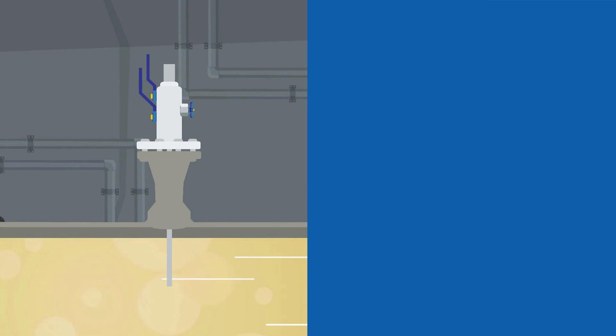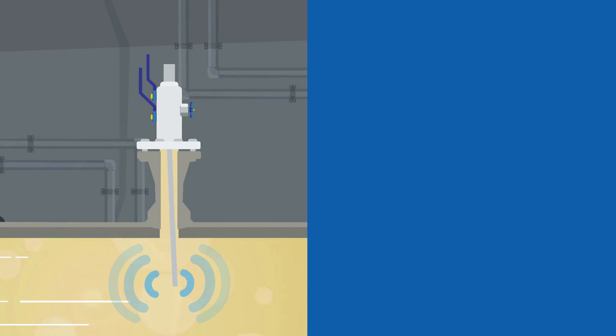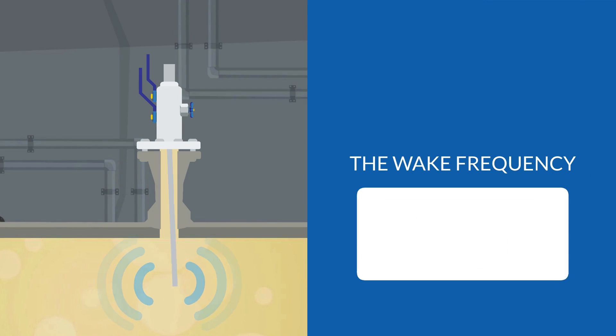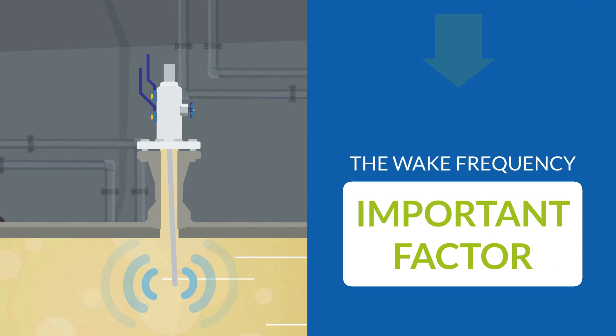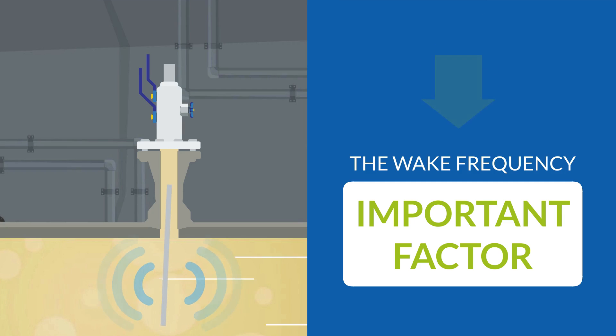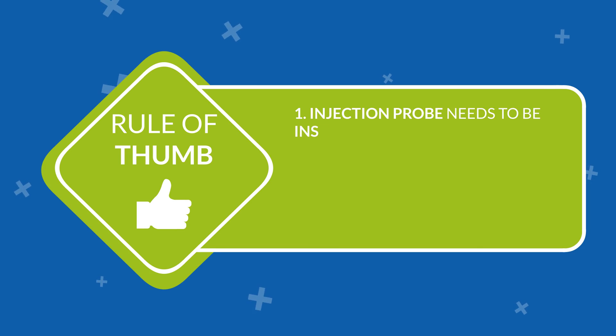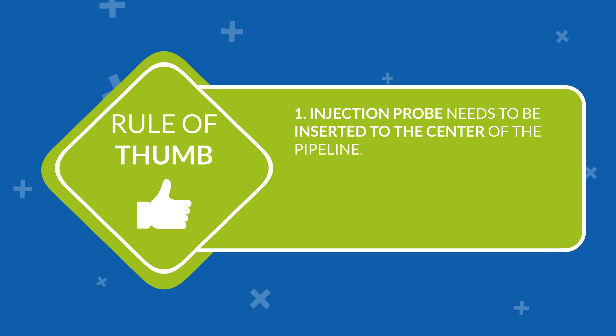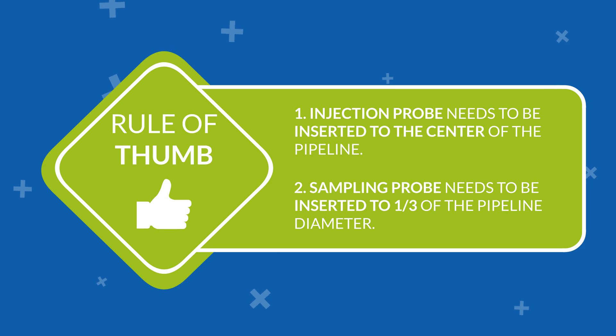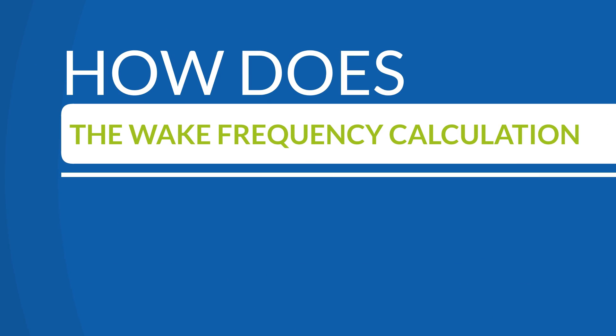Considering that an object inserted into the pipeline can prove disastrous if not properly designed, the calculation of the wake frequency becomes an important factor in the design of an injection or sampling DBB valve. The following rule of thumb applies for the length of the parts to be inserted into the pipeline: first, the injection probe needs to be inserted to the center of the pipeline; second, the sampling probe needs to be inserted to one-third of the pipeline diameter.